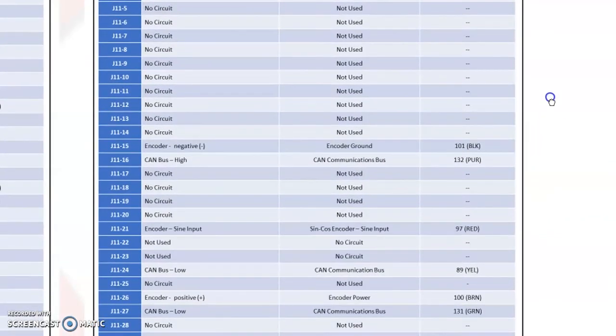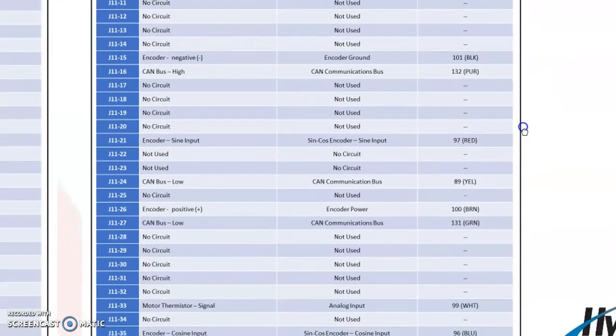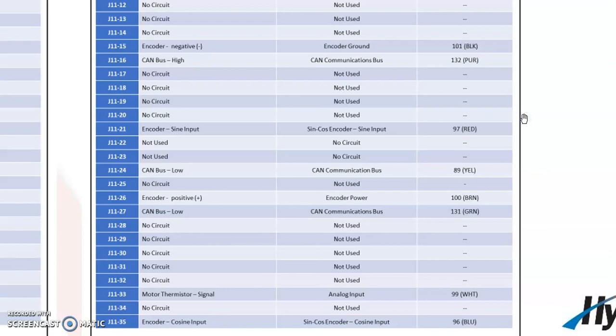So pin 15, I'll jump all the way down to 15, is again the encoder. So this is the motor encoder. This is the negative, the ground for the encoder. 16 is the CAN high. So this is the CAN line coming in from the generator controller. Pin 21 is the sine signal from the motor. 24 is the other end of that jumper wire for the CAN termination. 26 is the encoder power positive. 27 is the CAN low, or the other CAN line coming in from the generator controller. 33 is the temperature sensor thermistor, and 35 is also the cosine, so the other speed signal.